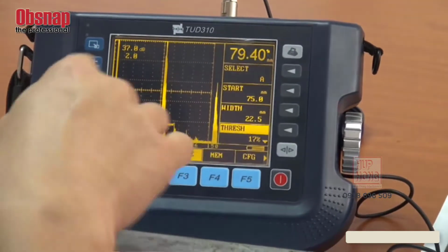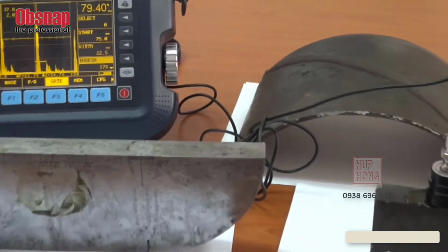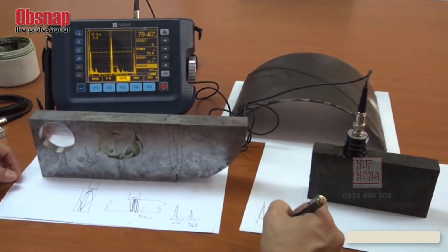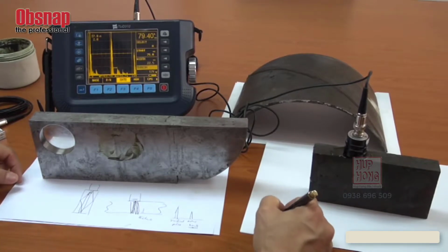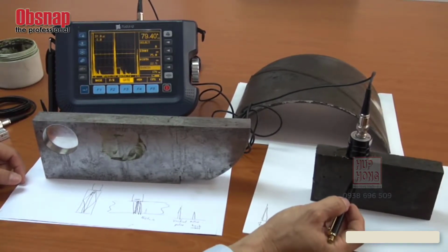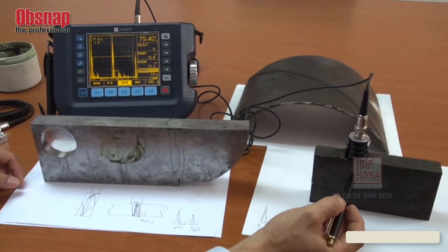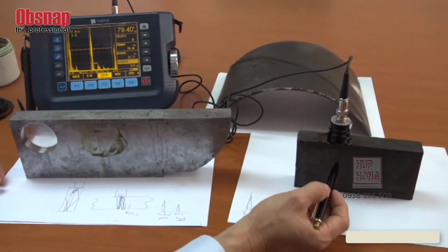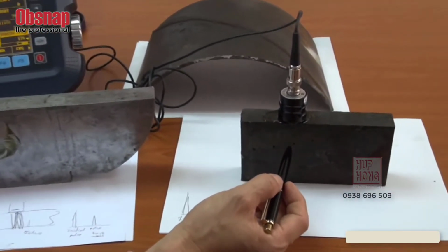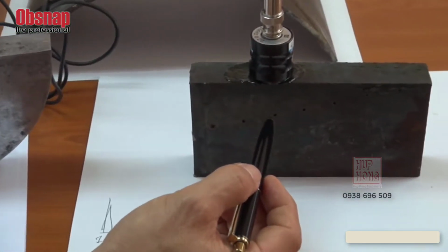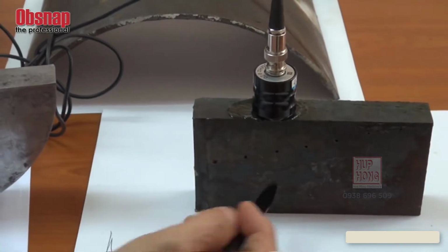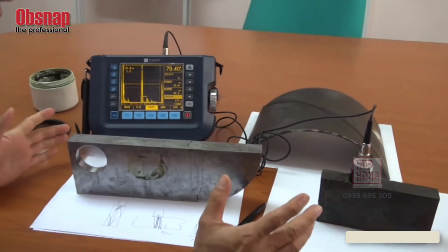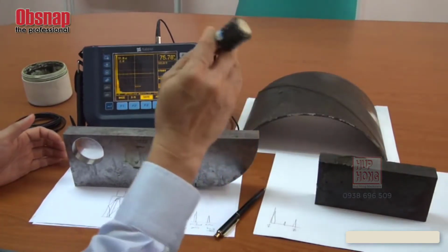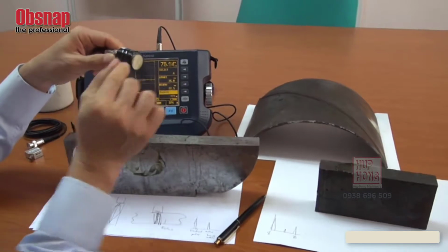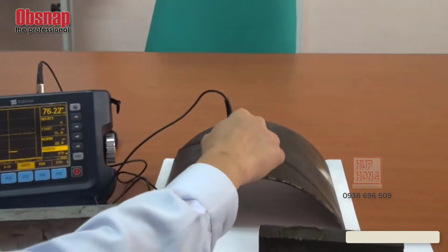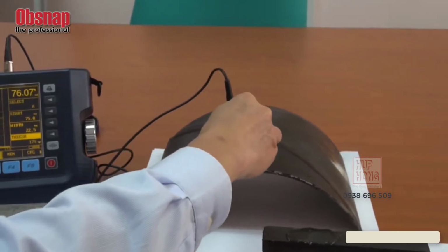So by seeing this, say this is the initial pulse, and this is actually the echo. Any pulse that you see in between is something blocking some of the sound wave. The sound wave that has been blocked and reflected back indicates a defect in there, either a crack or a cavity. Can you understand? Yes. Excellent. Any question? No. Now, there's a limitation for this straight probe. It cannot go to something so thin. Anything 6 mm and below is no good for this straight probe.